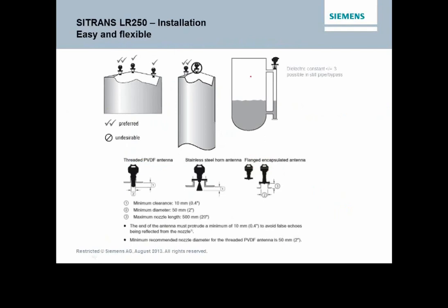A few other considerations when we talk about tanks is we can do these with stilling wells. For applications with solids, we can get into very low dielectrics. Again, the fully encapsulated, what I just talked about a little bit in terms of the nozzles and diameters. In the older style units, we could not be within the nozzle. So we had the LR250 styles, the non-hygienic styles. We had some limitations there that I was actually right into the process. Now, in effect, that horn is outside of the process in here, and the process itself is only seeing the lens. So major improvement in terms of the materials of construction. If I have an aggressive application, I don't have to go with an exotic alloy that's very expensive. I can stick with a Teflon unit here and be isolated from the process.